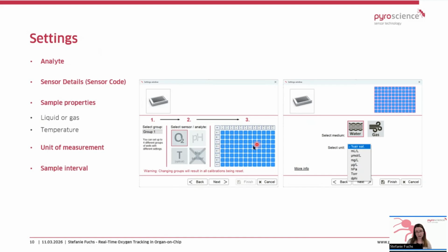Then you need to tell the software about the sample properties. As I said, you can measure in liquid or gas. And then also you can select the unit in which you want to measure. We offer quite a few of them. So here's an example of what you can do for water measurements. For example, you can have micromole per liter or milligram per liter, hectopascal, microgram per liter. So there's really a lot of options. For gas, there are other options which make more sense in gas measurements. And also you can set the sample interval, which can be everything from a few seconds to minutes or hours, depending on what you prefer for your measurement.